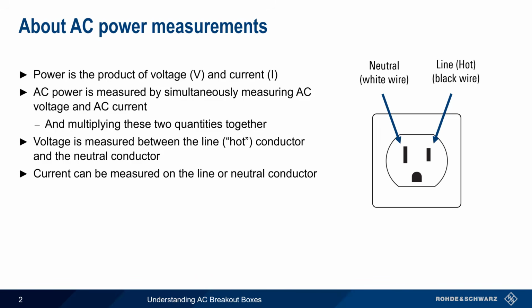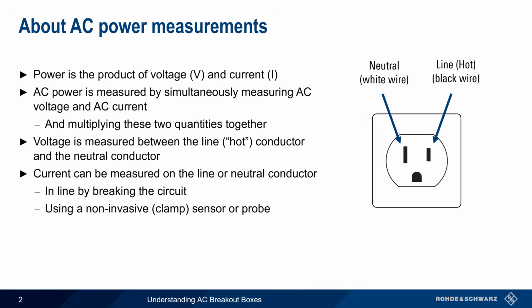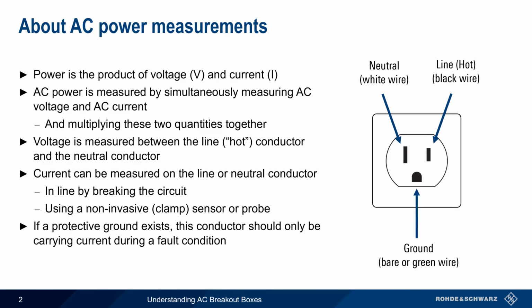Current can be measured on the line or on the neutral conductor, either by breaking the circuit and placing the measuring device in line, or by using a non-invasive clamp-style sensor or probe. Note that if a protective ground exists, this conductor should only be carrying current during a fault condition, and therefore this conductor is generally not used when making AC power measurements.